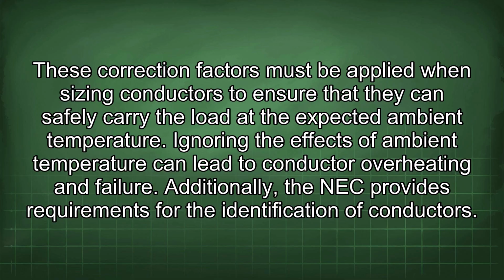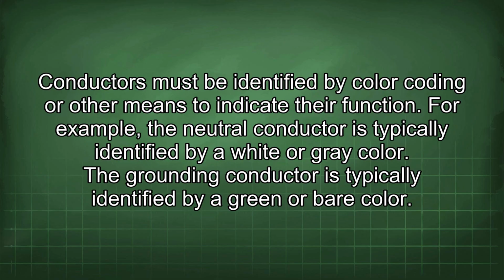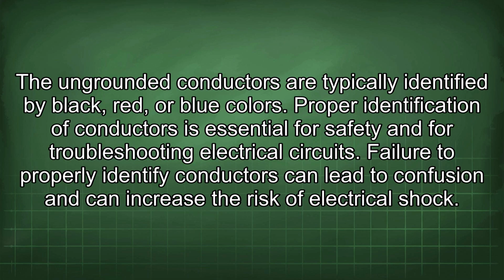Additionally, the NEC provides requirements for the identification of conductors. Conductors must be identified by color coding or other means to indicate their function. For example, the neutral conductor is typically identified by a white or grey color. The grounding conductor is typically identified by a green or bare color. The ungrounded conductors are typically identified by black, red, or blue colors. Proper identification of conductors is essential for safety and for troubleshooting electrical circuits. Failure to properly identify conductors can lead to confusion and can increase the risk of electrical shock.